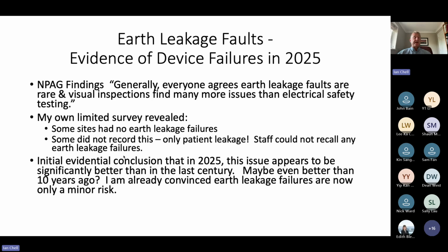So the initial evidential conclusion is that in 2025, this issue appears to be significantly better than in the last century. That's how long IPS has been about. And it's maybe even better than 10 years ago. So personally, I'm convinced earth leakage failures are no longer an issue. They're a minor risk, and the only risk comes from old medical devices. Okay.